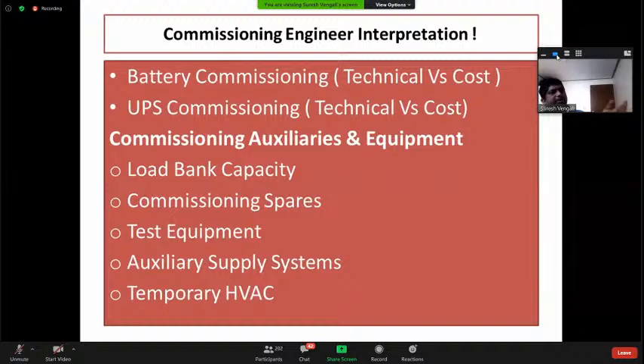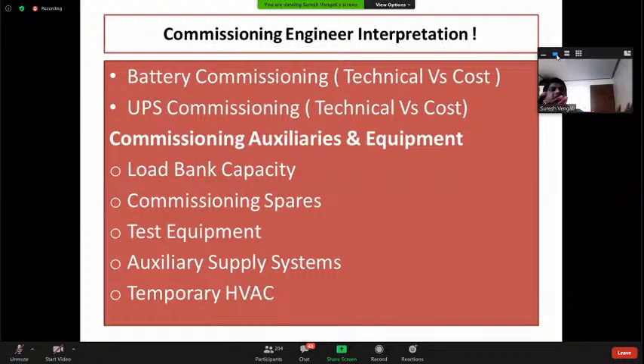For auxiliary power systems, sometimes you need additional supplies, so you need to check it - temporary HVAC. When you are installing any battery in a particular room, as I said before, you are running the battery at 20 or 25 degrees. When you receive a battery and store it, then you install it. When you're installing in a substation or any power plant, you don't have initial power supplies, so how will you provide the HVAC supply?